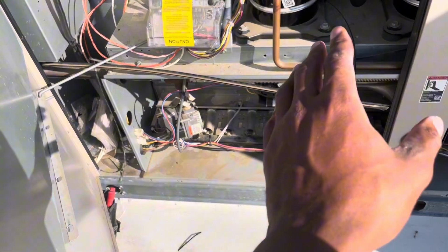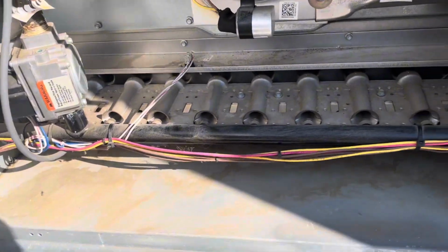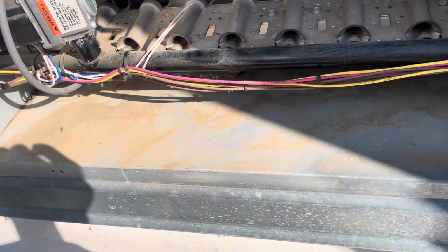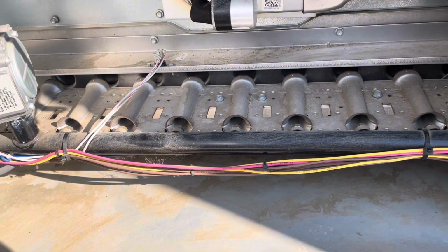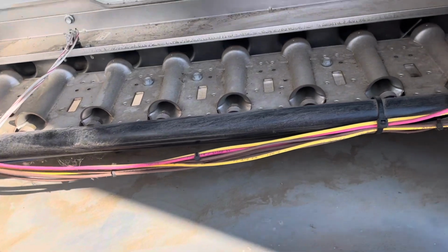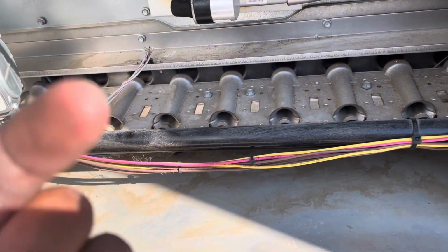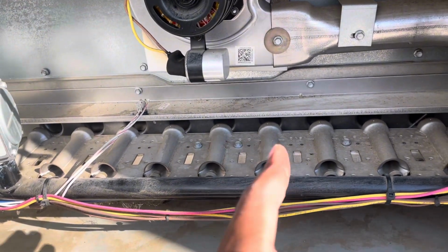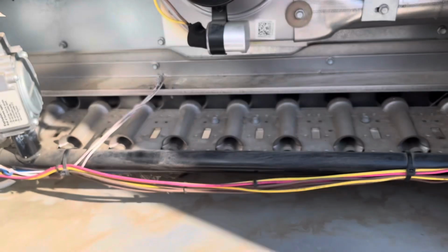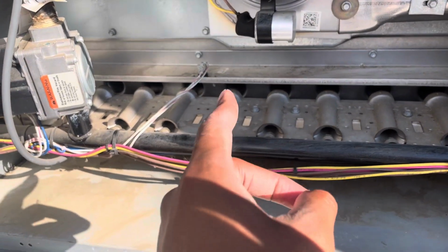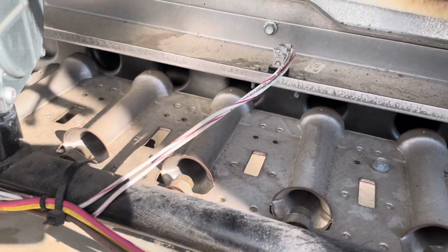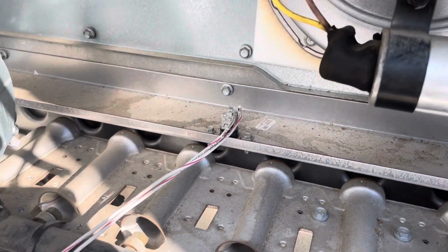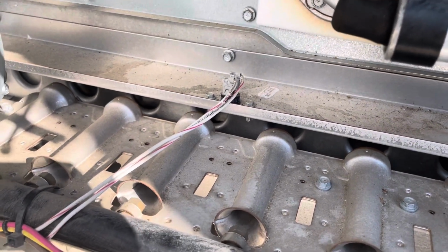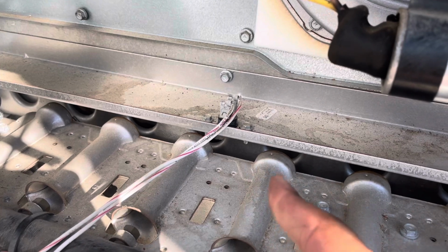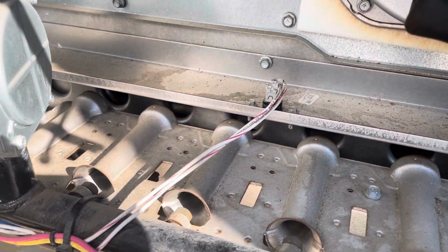Flame rollout switches. Their job, as the name suggests, is to detect a flame rollout. Typically you may have a flame rollout whenever there's a crack in the heat exchanger, and at that point you're pulling air through the heat exchanger and it's kind of forcing the flame out. The inducer motor pulls the flame in, but when you have cracks in your heat exchanger, that flame could be forced out, and when that happens, the rollout switch heats up because of the flame, and it opens and breaks the circuit, and it shuts everything off. So it's there for safety.